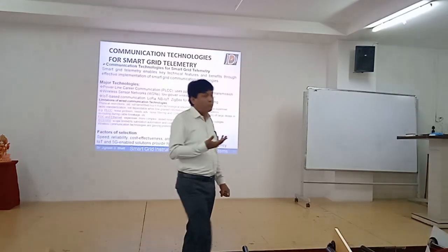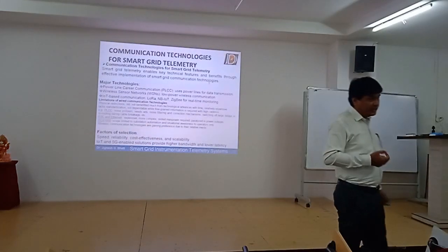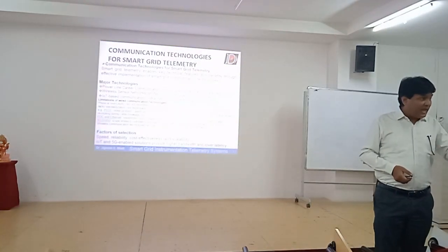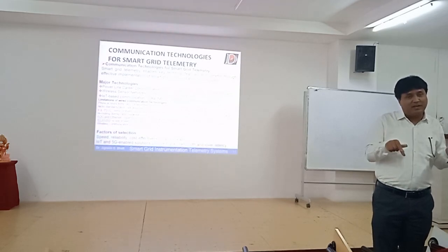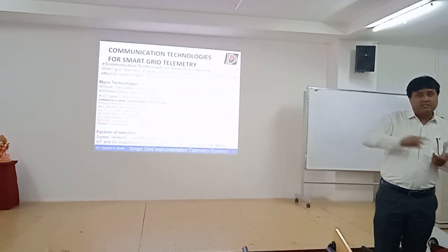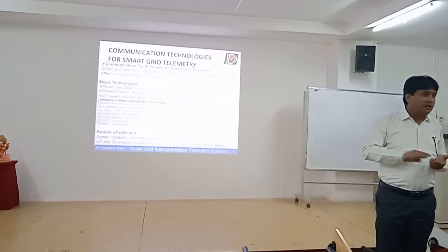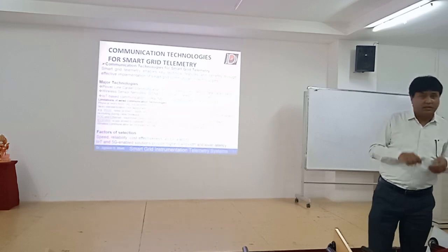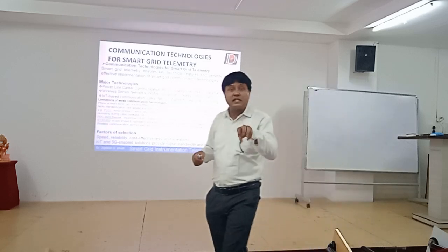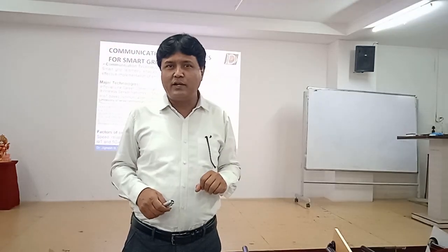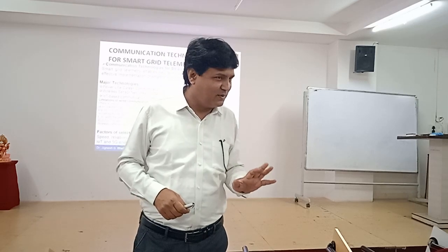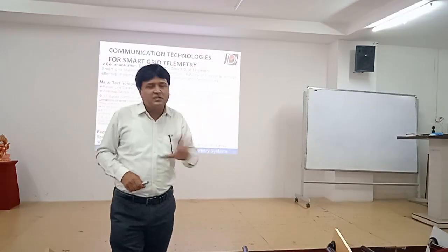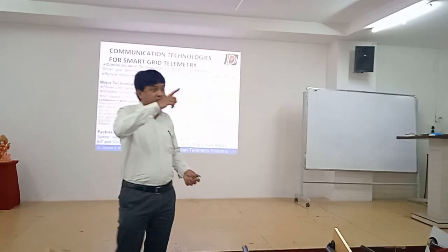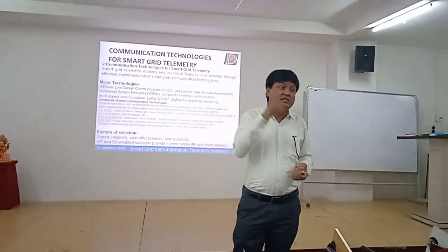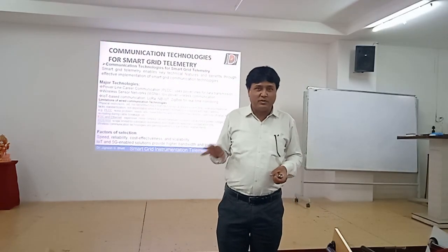Similarly, there is sniff mode, like a sniffer dog, which keeps checking the reading values. If large deviations are found among consecutive readings, sniff mode gets activated and starts sending alerts to the central control room or monitoring station that something is happening. For example, if readings change like 30, 25, 22, 45, is that possible? No, it's not. Something wrong is taking place, and that's why such large fluctuations are reported.